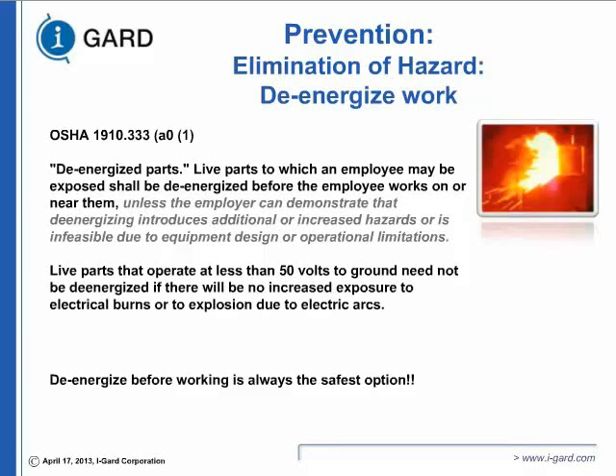OSHA also says live parts that operate at less than 50 volts to ground need not be de-energized. But there is a condition: if there will be no increased exposure to electrical burns or explosion due to electrical arcs. 50 volts and below is not considered fatal shock, but you can still get a flash hazard. Some of you who are used to working on cars probably have burned screwdrivers and burned fingers. Voltage is only 12 volts. So voltage is only a measure of the shock protection. Current is the one that decides what flash protection is needed.